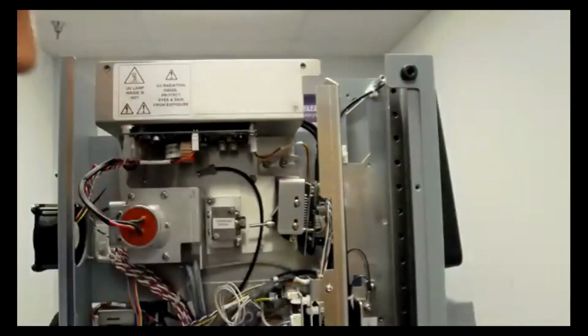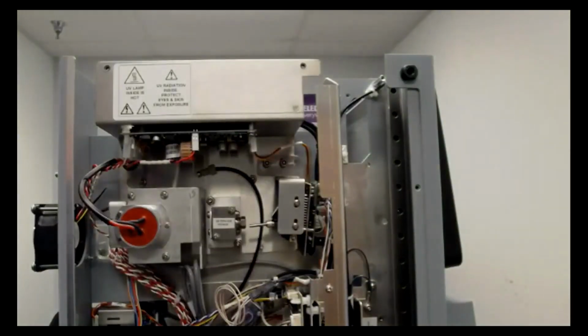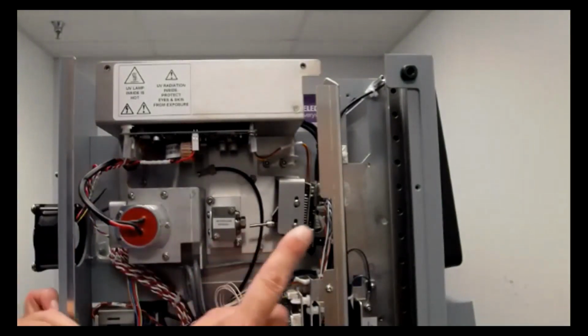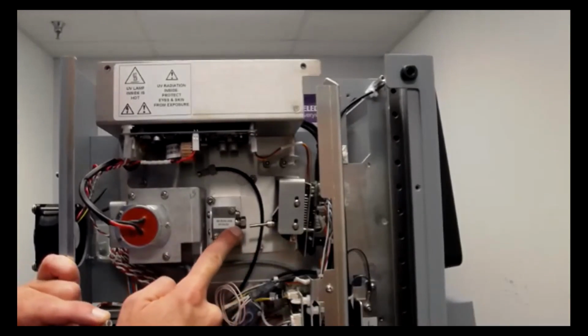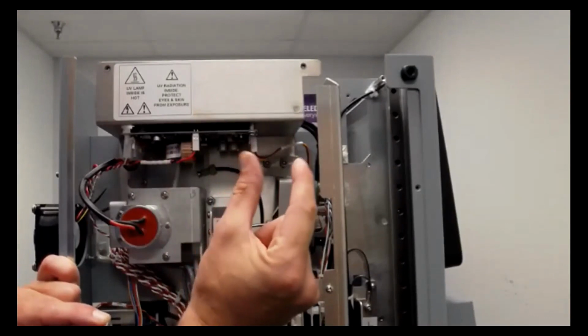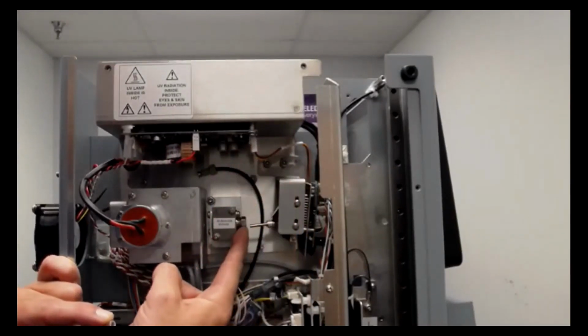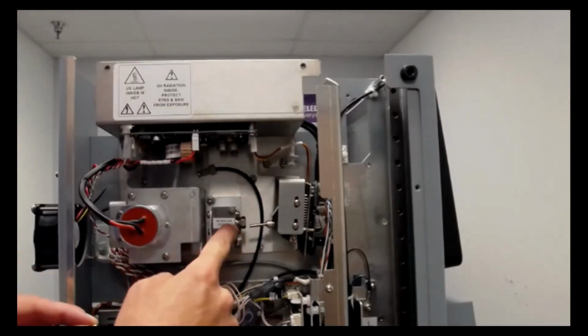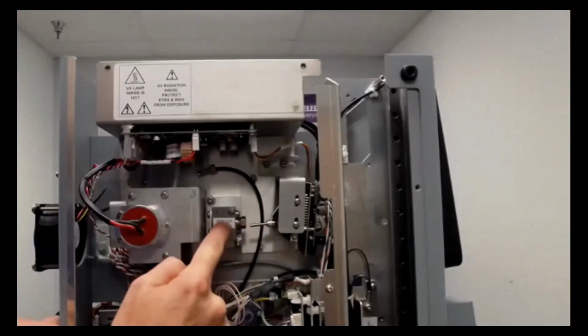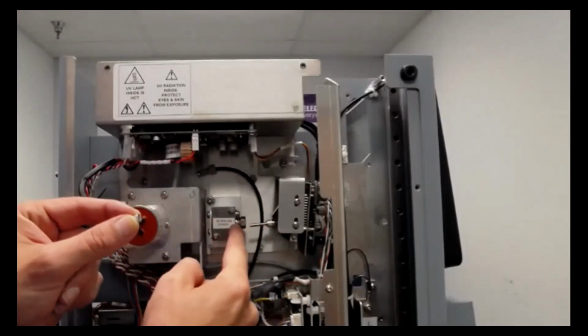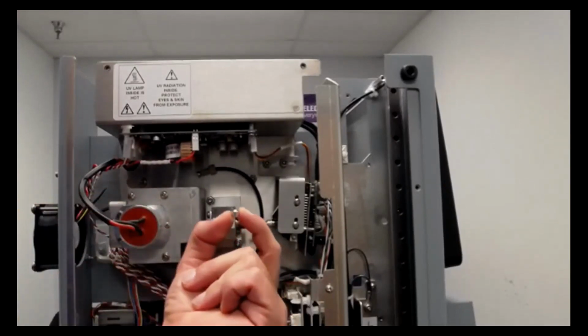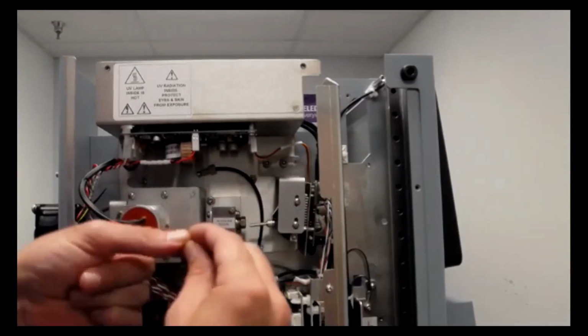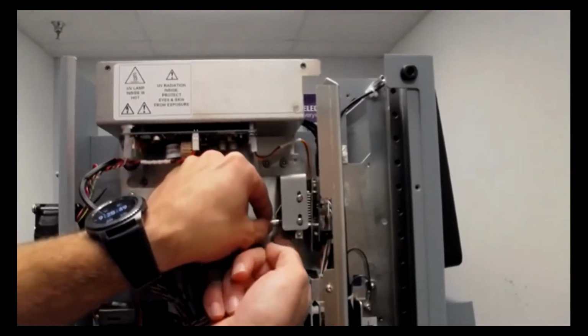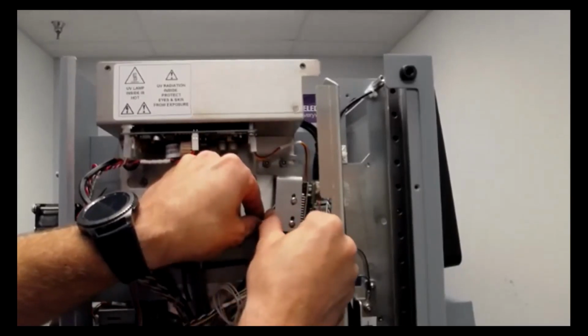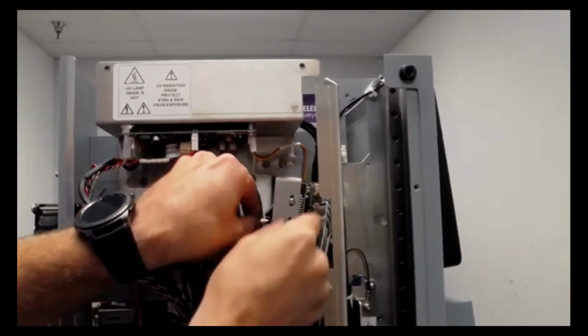Now, to find that spacer. Remember how I said don't lose the spacer? Okay, here's why. This is all in the manual, but there is what I call the sombrero washer here, and it's a large washer that's bent. And it goes in here, and this nut tightens onto it. Now, what that's doing is stopping this fiber optic rod here from hitting the quartz rod. But this nut and the sombrero washer work in tandem with this spacer. They work together with it. So if everything's lined up and correct, then this fiber optic rod will not be hitting the quartz rod inside the flow cell. So I've got that spacer on there.